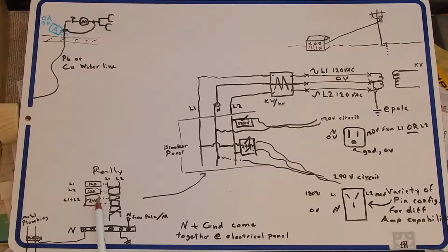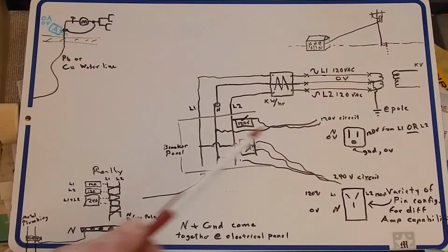And then a 240 breaker hogs both spots and connects to both an L1 and an L2. So every other breaker is L1, L2, or here L1 and L2, all the way down on both sides. That's typical. There's going to be variances.